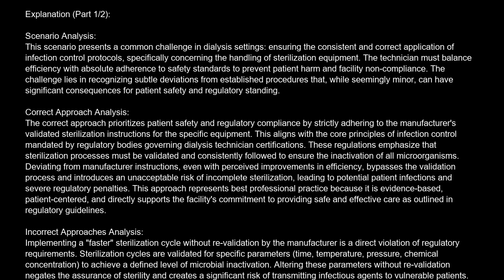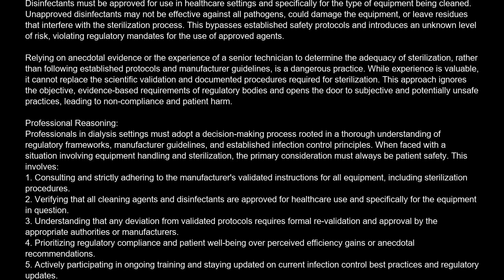Using a different, unapproved disinfectant for cleaning reusable equipment before sterilization, even if it appears to be effective, is also a critical failure. Disinfectants must be approved for use in healthcare settings and specifically for the type of equipment being cleaned. Unapproved disinfectants may not be effective against all pathogens, could damage the equipment, or leave residues that interfere with the sterilization process.